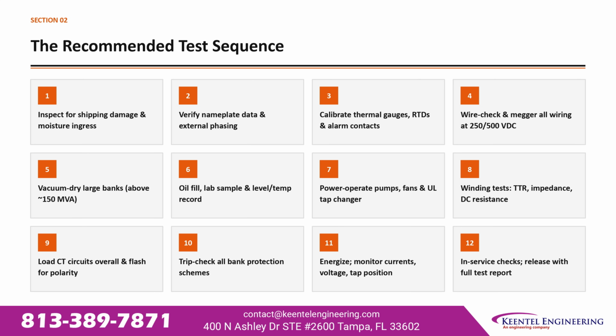Inspect for shipping damage and moisture ingress. Verify nameplate data and external phasing. Calibrate thermal gauges, RTDs, and alarm contacts. Wire check and Megger all wiring at 250 to 500 volts DC. Vacuum dry large banks above roughly 150 megavolt amperes. Fill with oil, take a lab sample, and record level and temperature. Power operate pumps, fans, and the tap changer. Run winding tests, TTR, impedance, and DC resistance. Load the CT circuits overall and flash for polarity. Trip check all bank protection schemes, energize and monitor currents, voltage, and tap position. And finally, run in-service checks and release with a full test report.